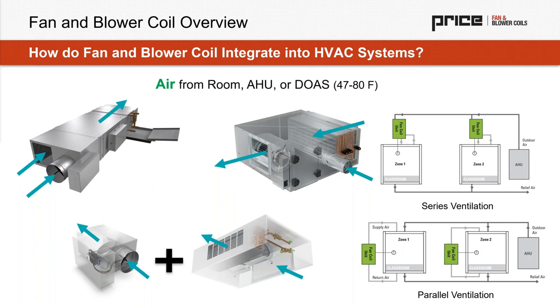So parallel ventilation has the fan coil getting return air directly from the zone, conditioning it and resupplying it to the space. If we think about a room mounted fan coil, where we would have a fan coil under a window or exposed mounted in the ceiling with a painted and architecturally finished casing, those applications will also have another ducted system from an air handler that's going to be providing outdoor air.